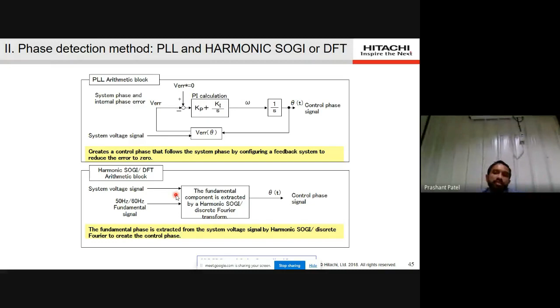Having harmonic SOGI and DFT block. Normally, if you want to synchronize our signal to 50 Hz, in India it's 50 Hz, or in the USA 60 Hz. That is our reference signal, and that is our system voltage signal. The SOGI and the DFT algorithm extract only the positive sequence component of the fundamental frequency, and try to synchronize your converter signal with that component. That's why it's very accurate, and it maintains synchronism in any worst condition of the electrical grid. So this is just one example of a simple PLL block.